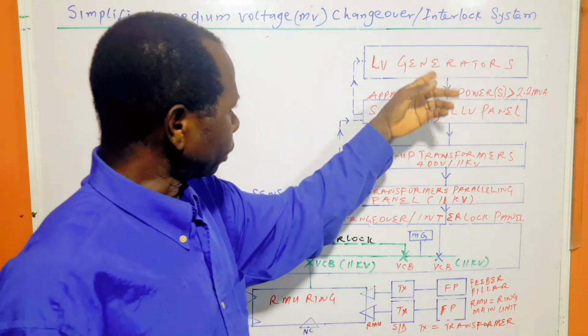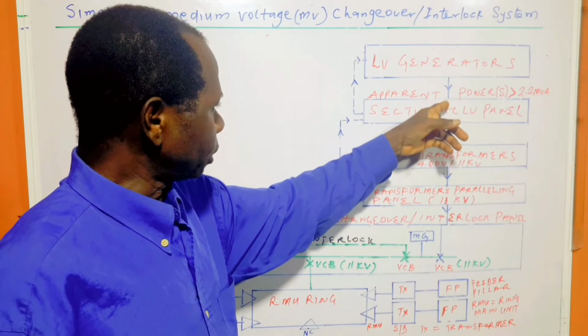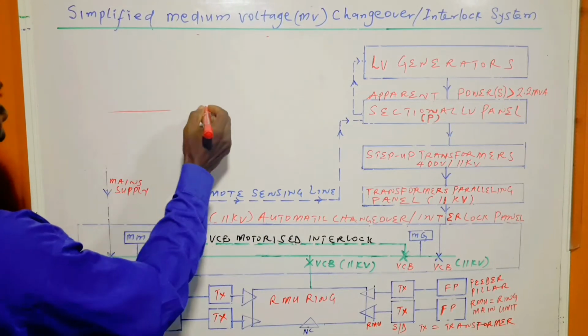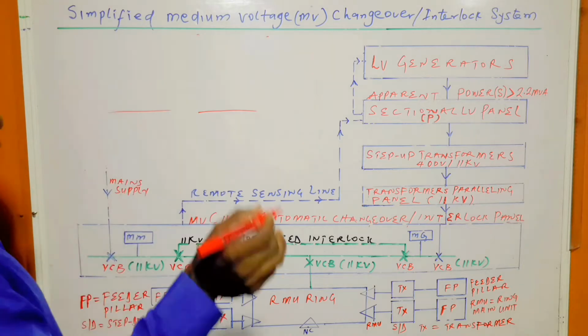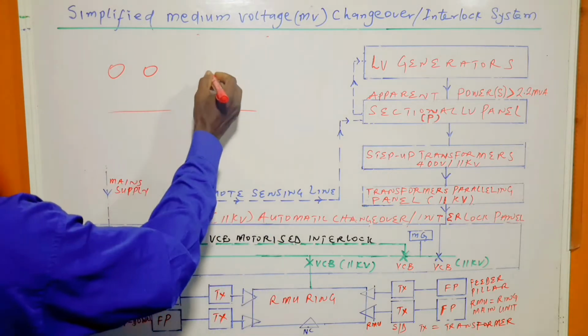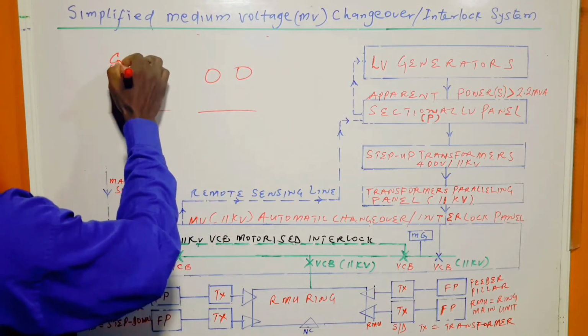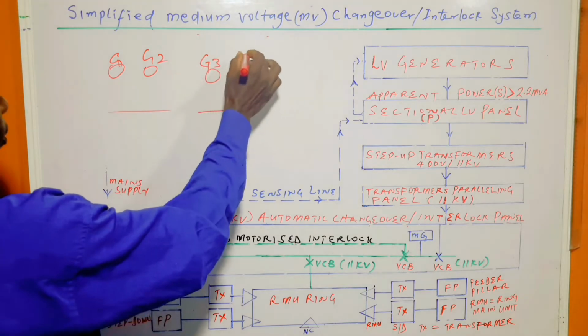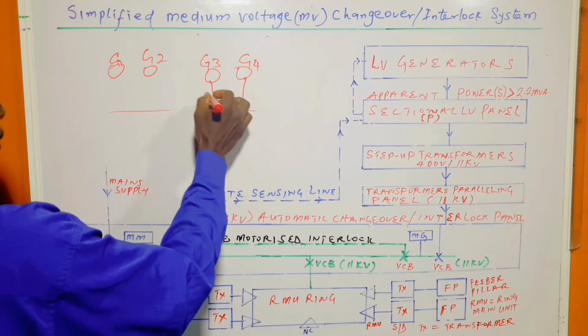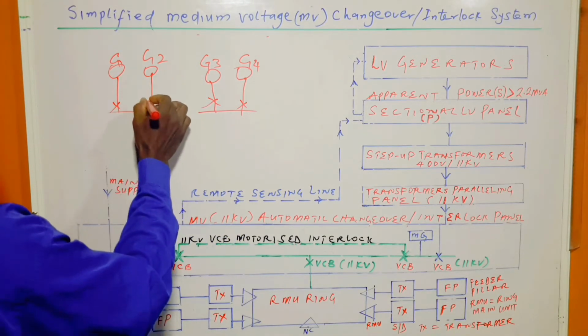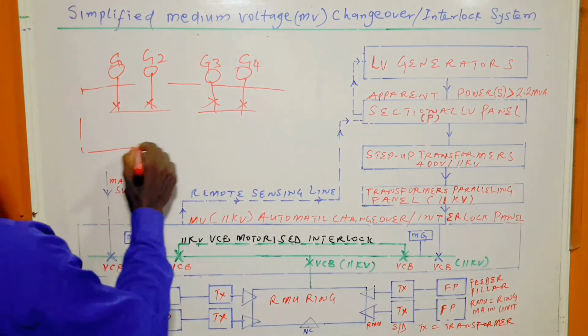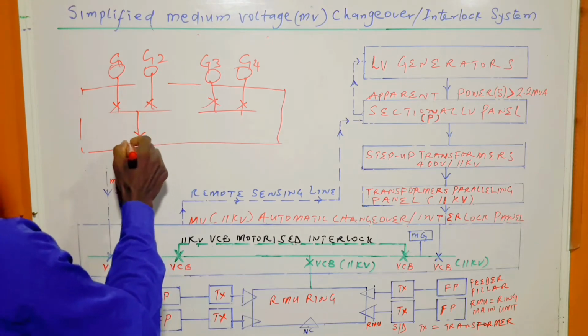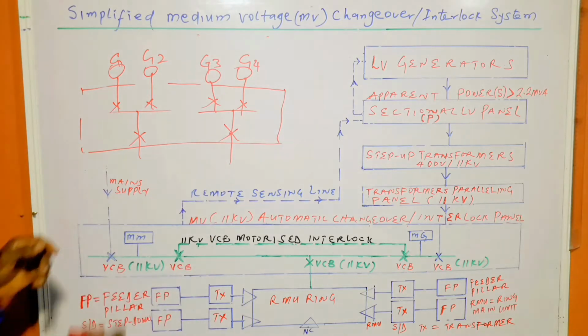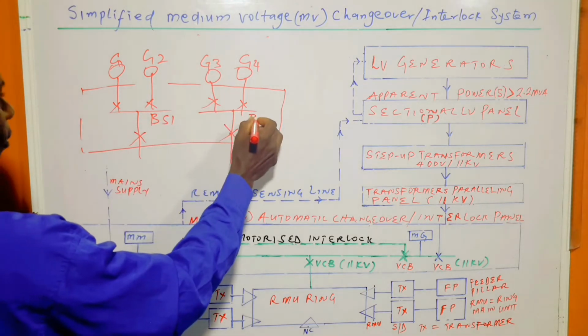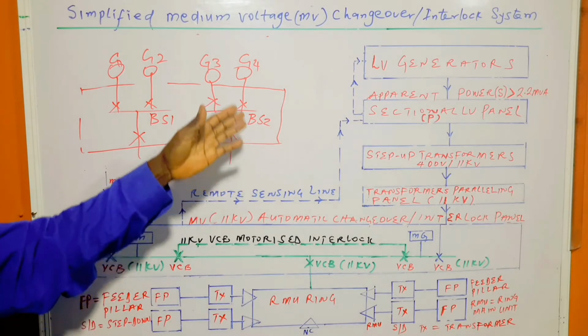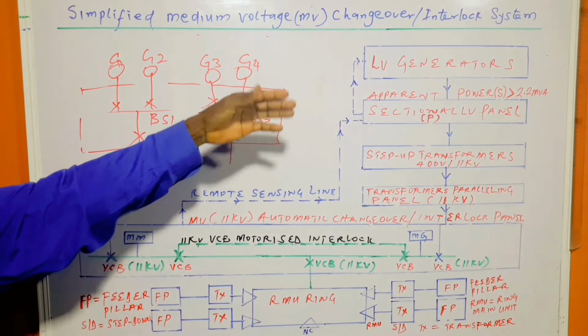So the output of the generators passes through this sectional panel. What we call a sectional panel is that the main busbar of the panel is divided into sections. So generator, generator, generator: G1, G2, G3, G4. This one comes here through a circuit breaker, and this one delivers to this section through this circuit breaker. So this is the panel, and then we have the outgoing through this circuit breaker. So we have bus section 1 and bus section 2. The sections could be more than 2 depending on the load or the power requirement.